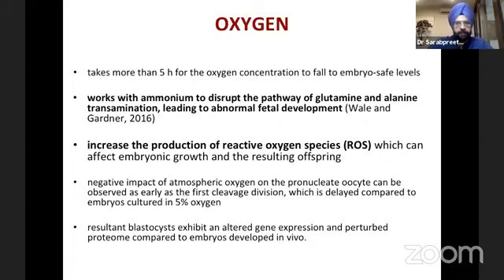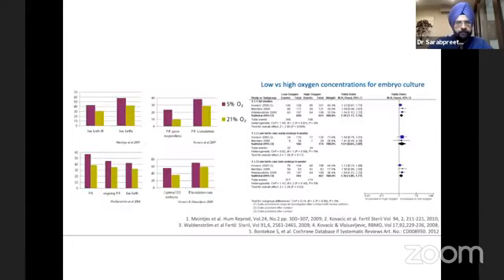It also increases the production of ROS, which can affect embryonic growth negatively. So the norm is that you should use oxygen at 5%. Unfortunately, I was reading the data on these incubators. Only less than 25% of incubators are with oxygen control or low oxygen incubators. 75% or more are single gas incubators, which are used across the world. This meta-analysis shows that 5% oxygen does better if you take indices such as live birth rate and implantation rate. Even if you do a cleavage transfer or a blast transfer, low oxygen incubators do much better and they should be used.